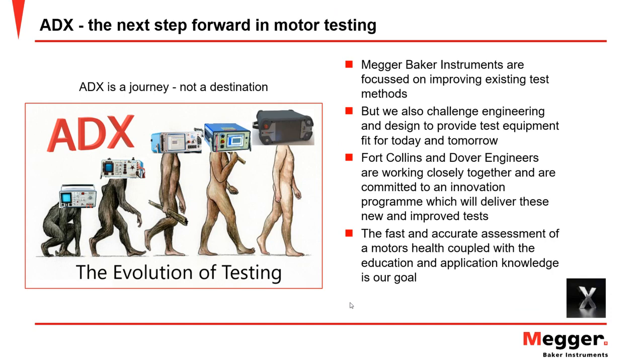So if you imagine 2,000 or 3,000 volts times 8 times full load current, the startup condition for an electric motor is the worst the motor will ever see. It's the most stressful time. So what our testers try to do is, without the power of the joules of energy that we get from volts times amps equals power, right? So during that startup period, we've got 800 amps times 2 or 3,000 volts. That gives us very, very high wattage, lots and lots of kilowatts of power.